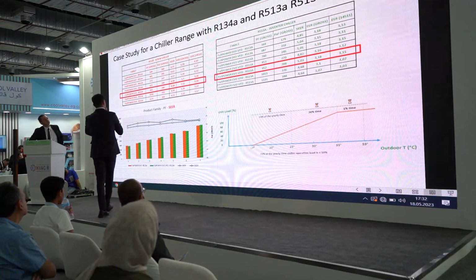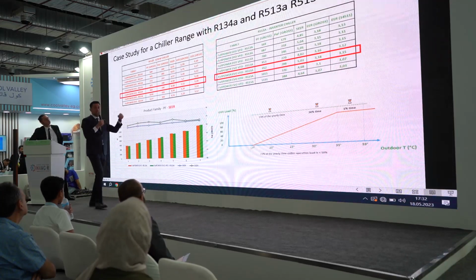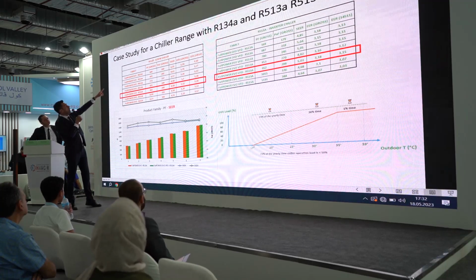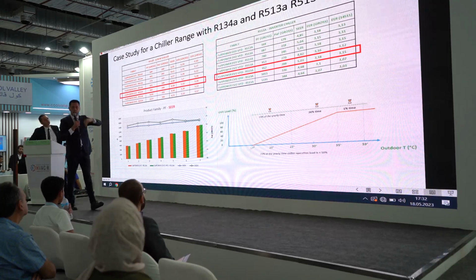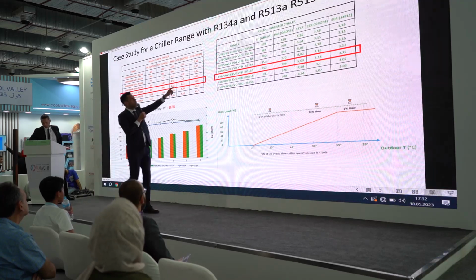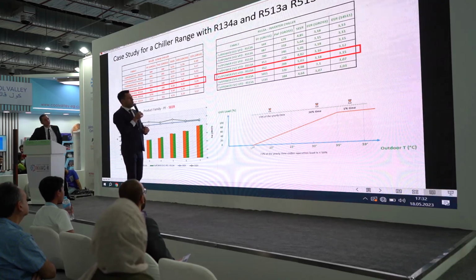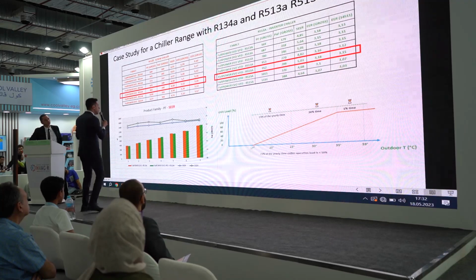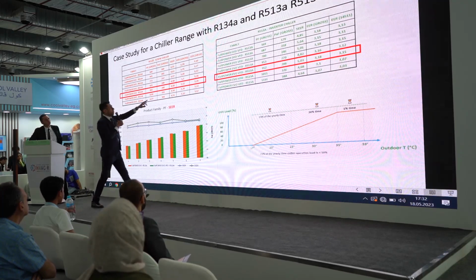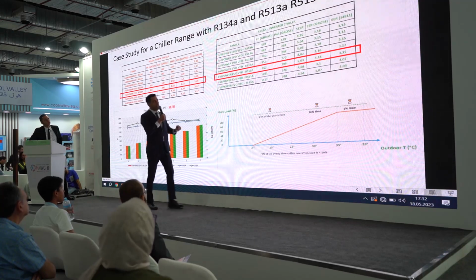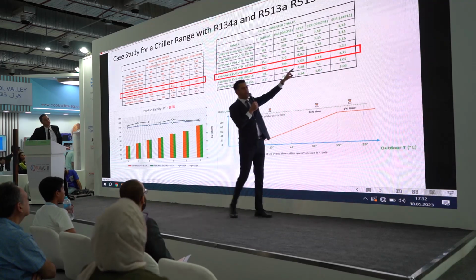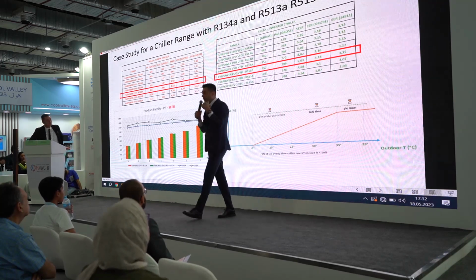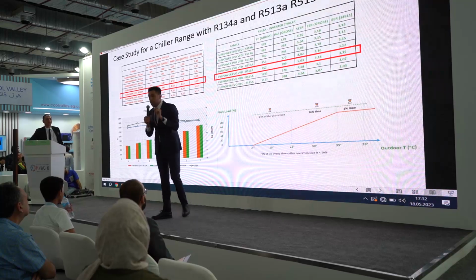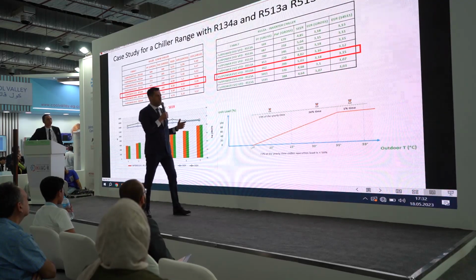So if we come to this point, now the comparison is the second and third chillers. 513A refrigerant, a new one, lower GWP, the same refrigerant, but this is VFD. So what I'm trying to underline here, as you see, because of VFD, for example, it is 4.58 seasonal energy efficiency, then 5.03. So higher energy efficiency, especially at part load. Why am I talking about the part load?